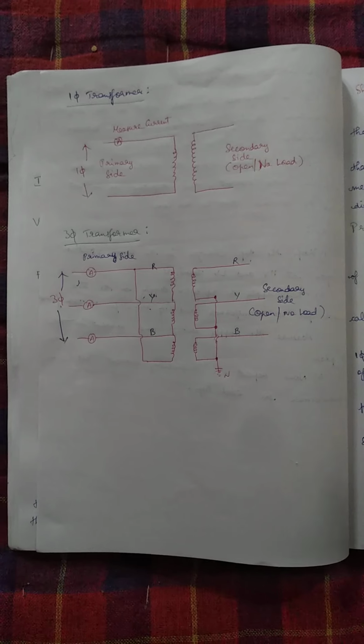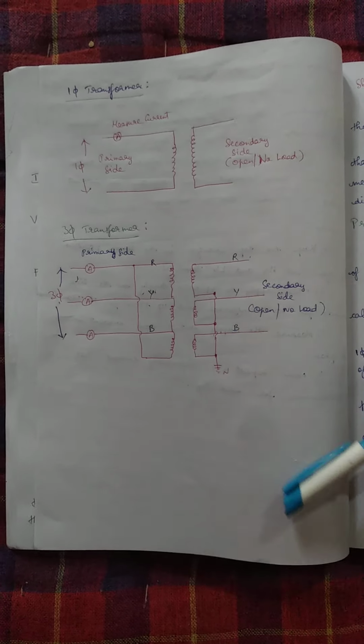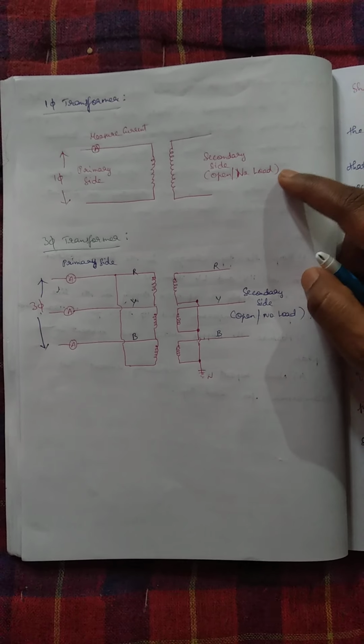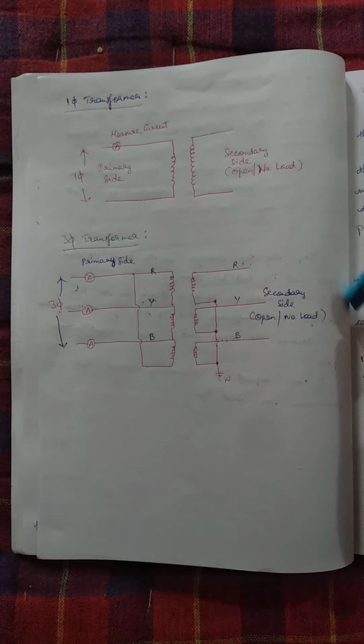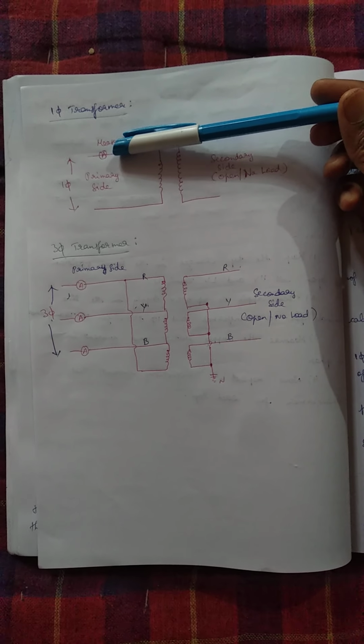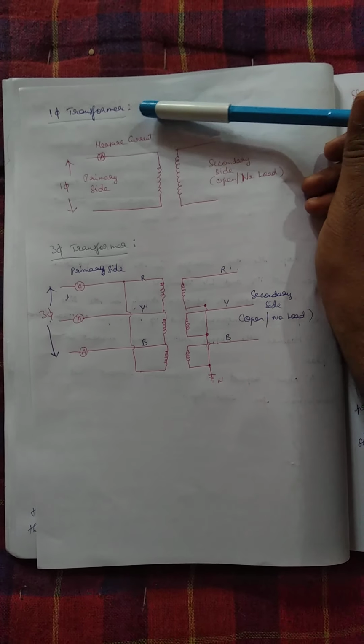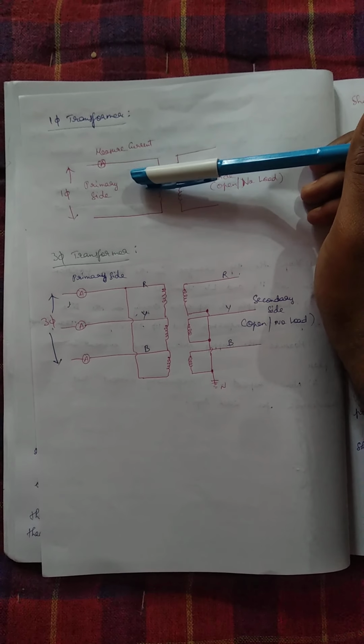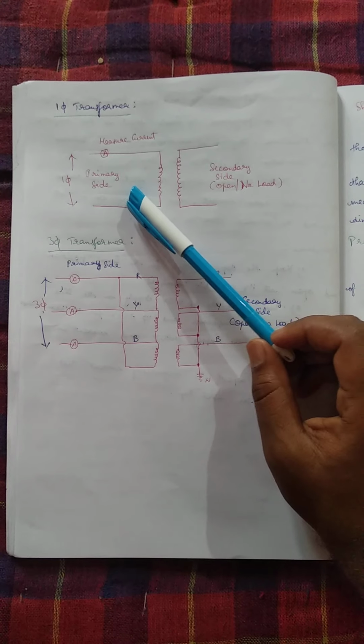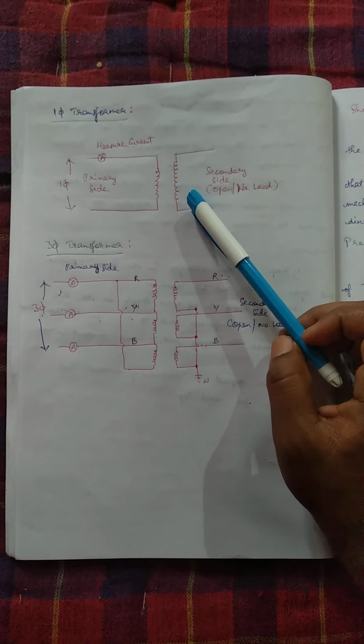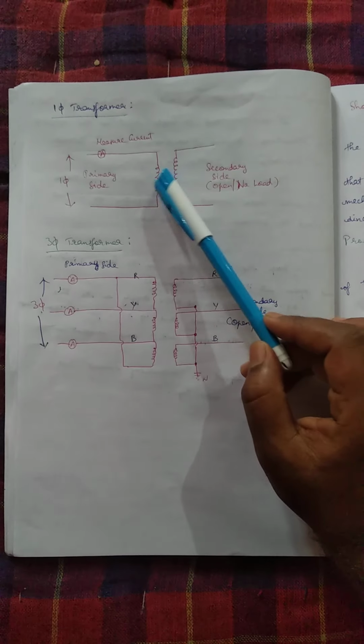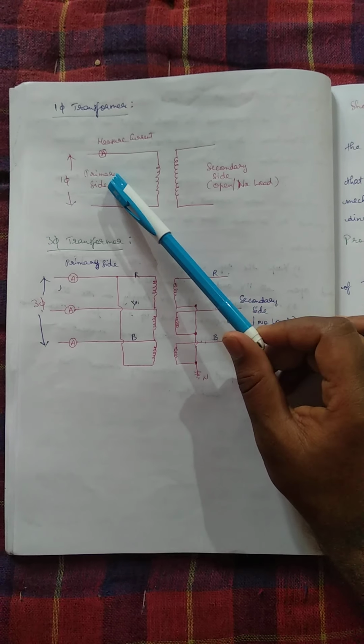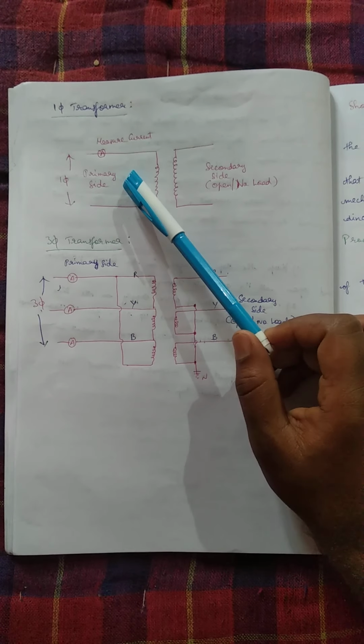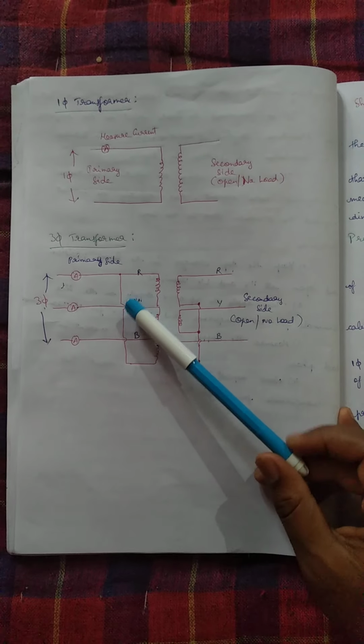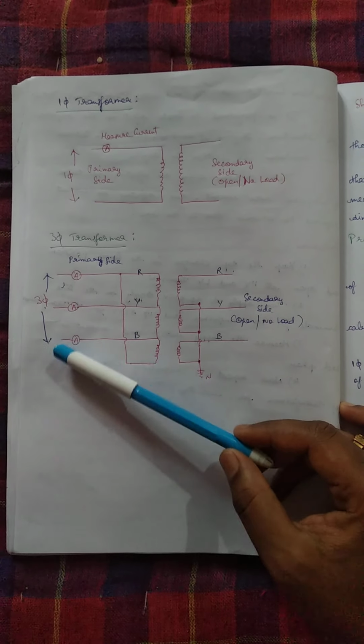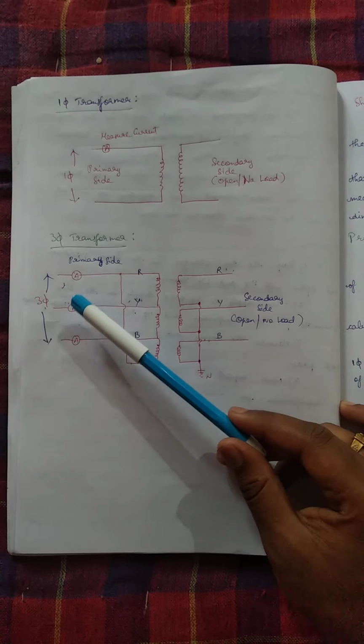This is the connection of your single phase and three phase transformer. As you know, I have kept the secondary side open and am injecting the voltage on the primary side and measuring the current by ammeter or tong tester or leakage tester on the primary side of the transformer. Here the secondary is open, so the current flowing in both sides will be the same, so there is no problem measuring on the primary or secondary, whichever it may be. And also for a three-phase transformer, in the same way, we are injecting a three-phase voltage and measuring the voltage and current.